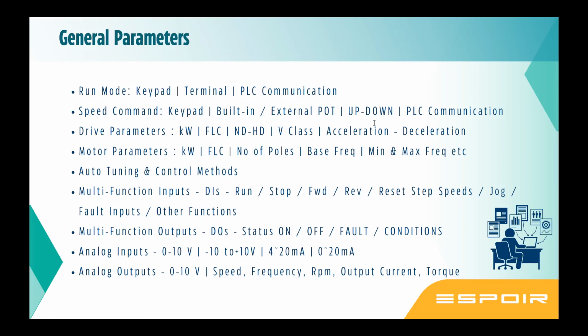You have to define what is going to be your speed reference input. You need to define it accordingly because the drive is blind. The default setting is there, say 0 to 10 volt. If you are going to give current, it is not going to recognize it. So you need to define that, otherwise the drive is blind.